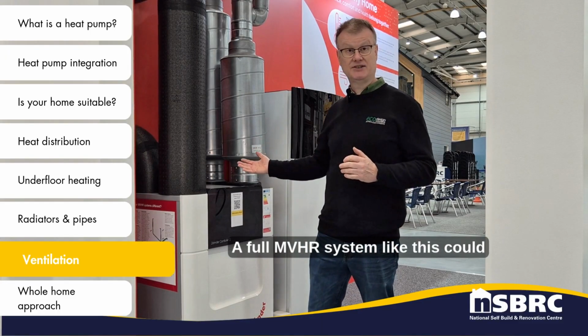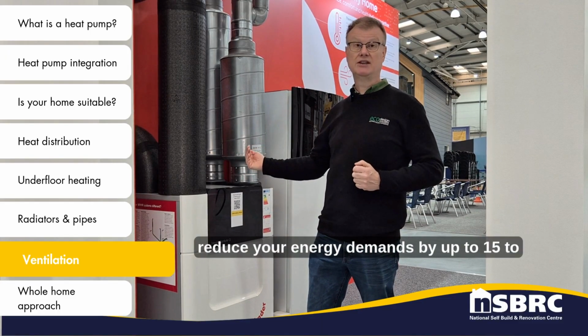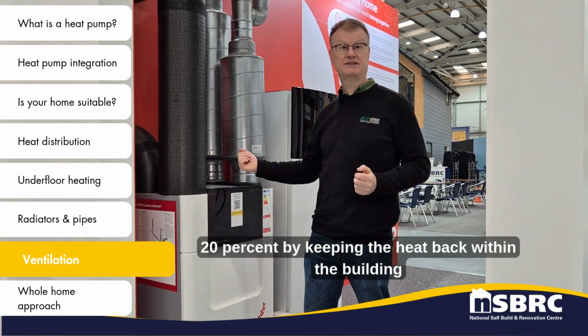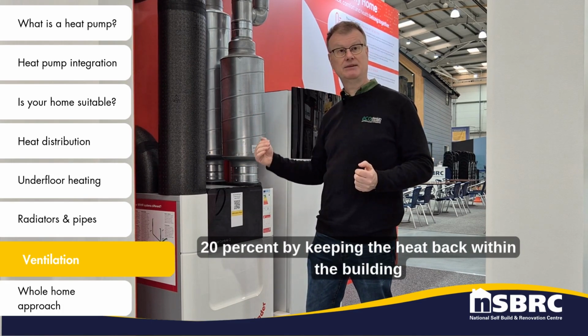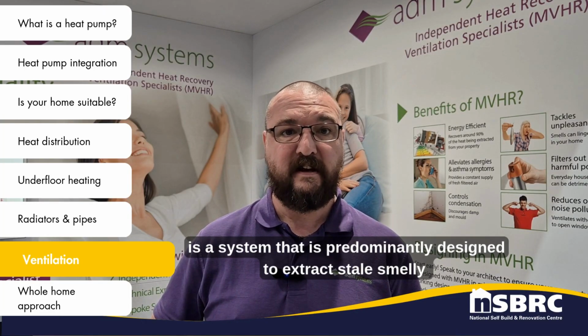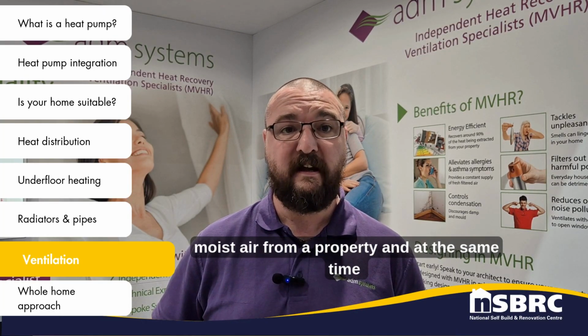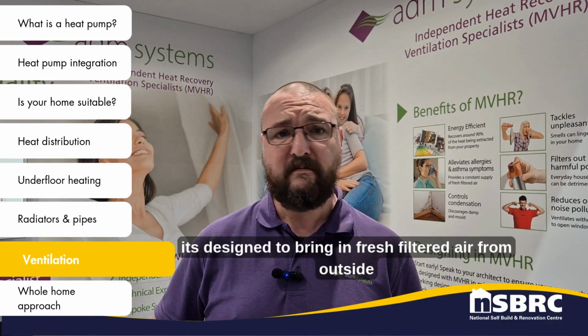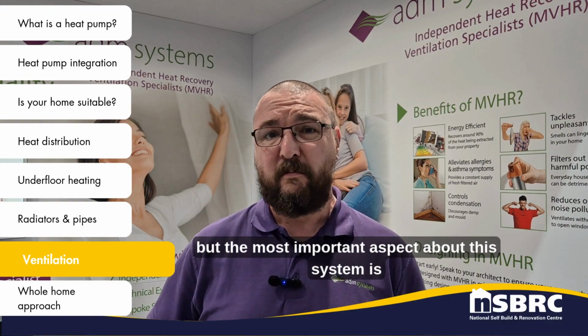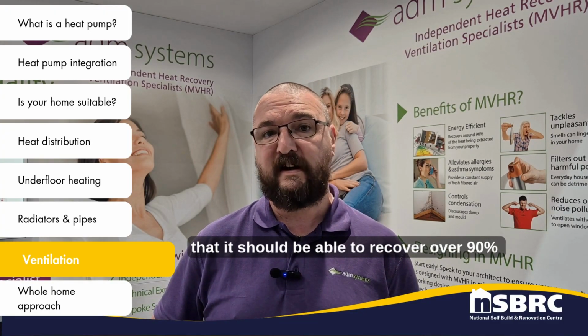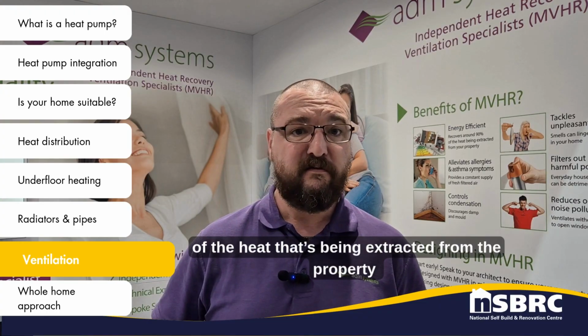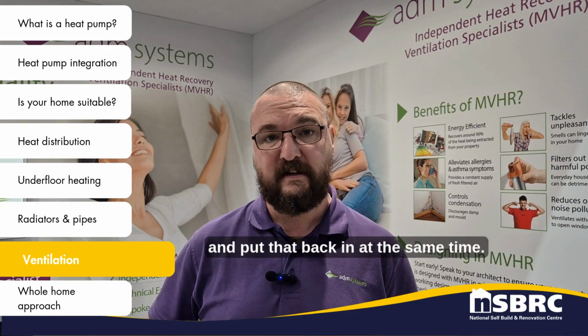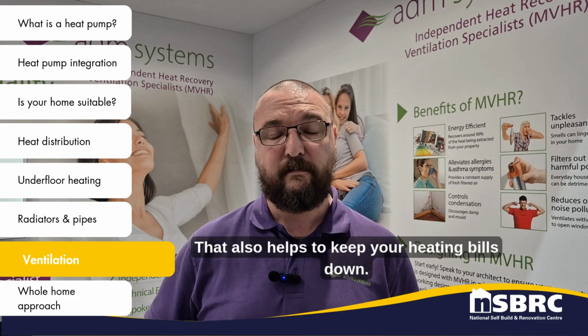A full MVHR system like this could reduce your energy demands by up to 15 to 20% by keeping the heat back within the building. Mechanical ventilation systems with heat recovery, or MVHR for short, is a system that is predominantly designed to extract stale, smelly, moist air from a property, and at the same time it's designed to bring in fresh filtered air from outside. But the most important aspect about this system is that it should be able to recover over 90% of the heat that's been extracted from the property and put that back in at the same time. And that also helps to keep your heating bills down.